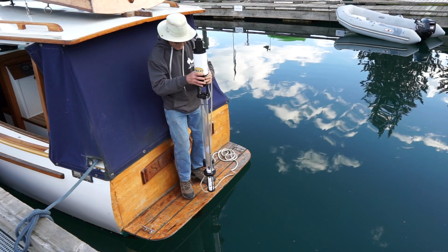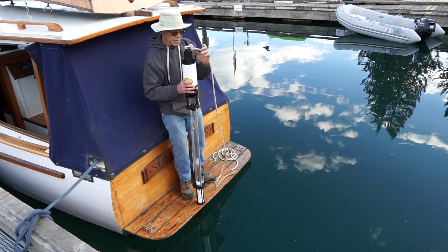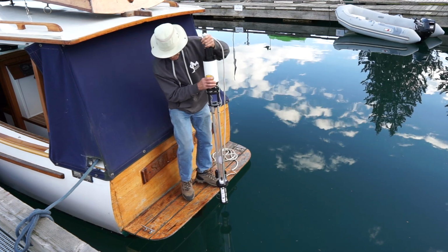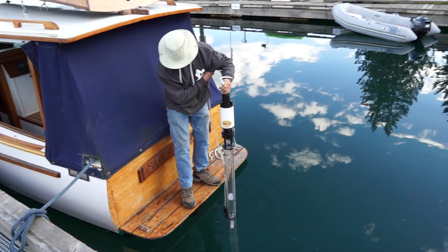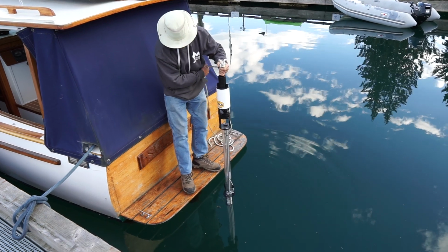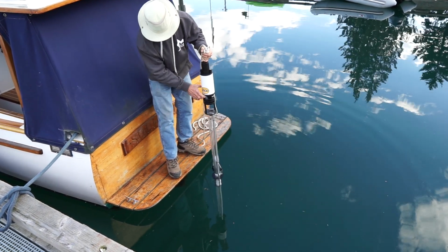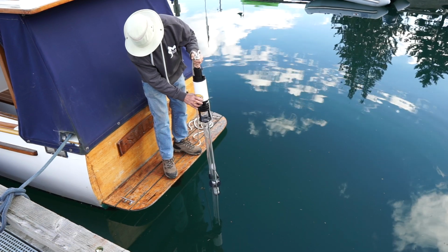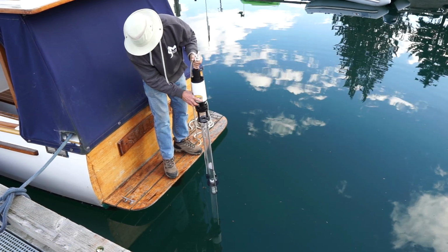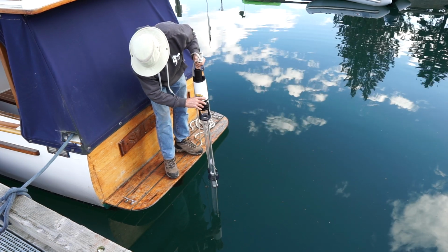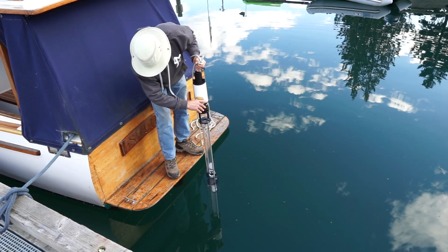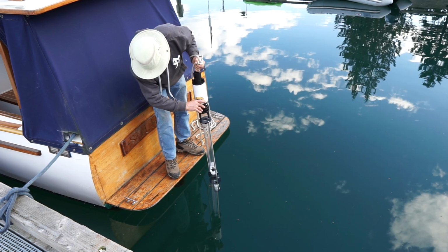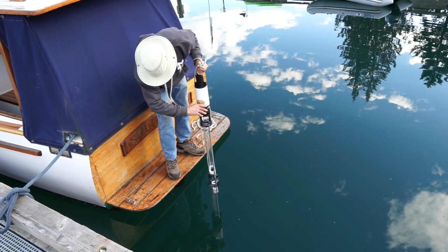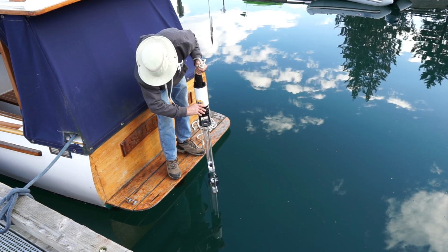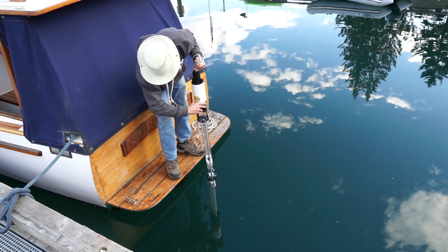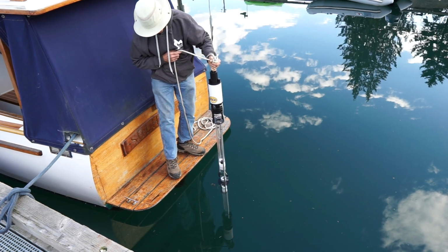I'll run it manually so you can see it operate. So this is a simulation of going to 3 meters. We're lowering with the rope, which I've marked to simulate 3 meters, or to show me that it's at 3 meters, because I don't have any feedback. And the pressure transducer comes on and lifts the winch, lifts the plug up into the tube, and the water directly below the tube follows. The second plug enters, and once it enters, the optical sensor sees the plug enter and shuts off the winch.